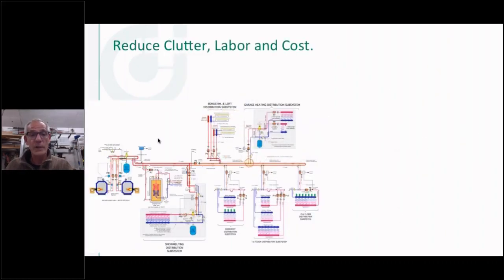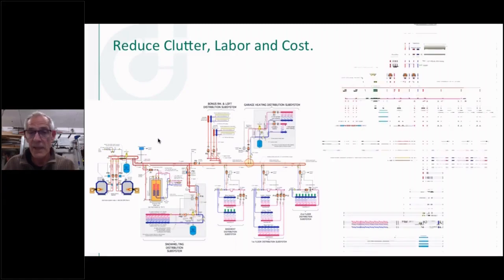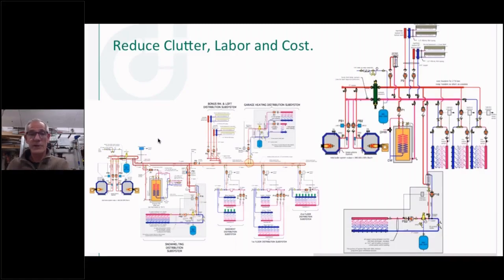And so we're going to take that drawing there. I just kind of scrunched it up so you can't read as much on it. And now we're going to put a hydraulic separator in there. And look what we did to all the piping and all the labor that you'd have to do on this job. And also, we've taken out our air separator. We've put a dirt separator in that. I don't even know if there was a Y-strainer or any kind of separator in this one here.